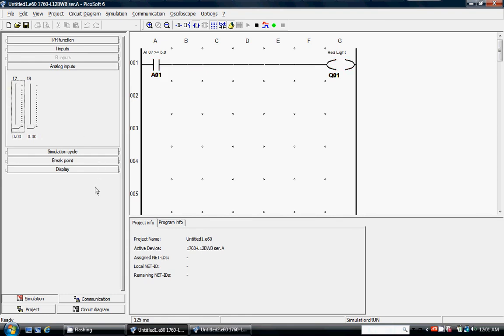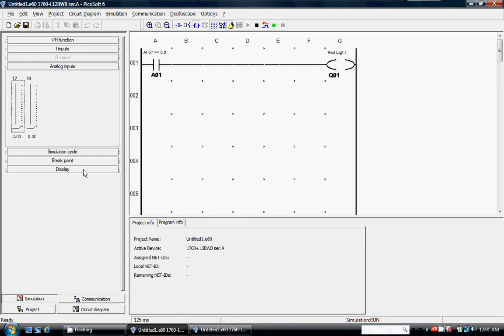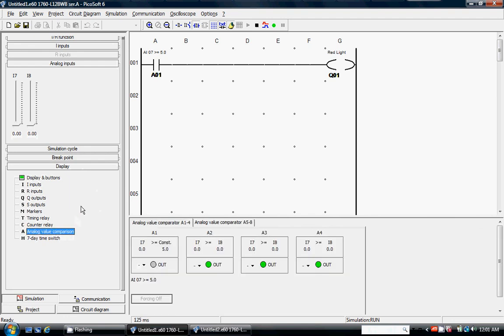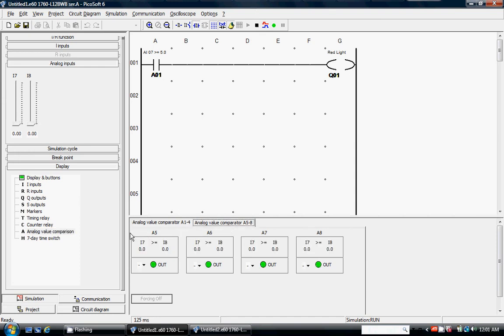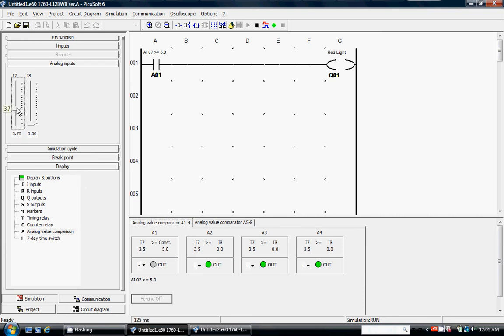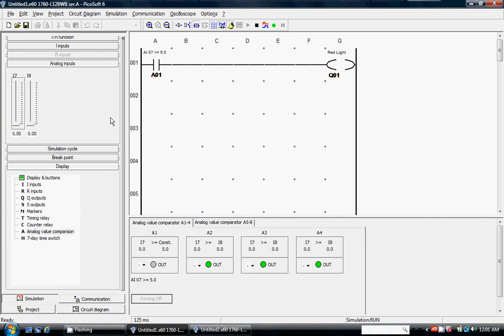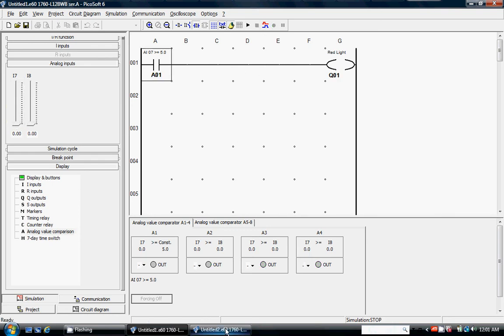I do have a display value here. If I go to Analog Value Comparisons, here's my A1 compare. I want to go to A7, I'm sorry, I want to go to A1. And here's my value, we can see that the value on I7 triggers at 5.0, so it's really no different than what we see on the screen. So, I'm going to stop the simulation here, and I'm going to go to a more complex example.